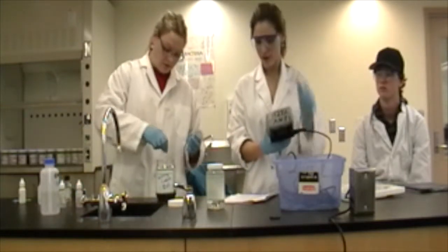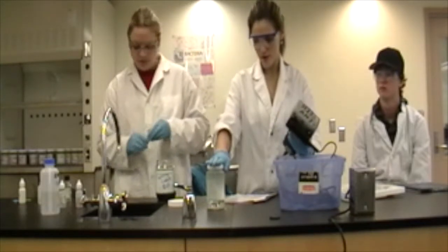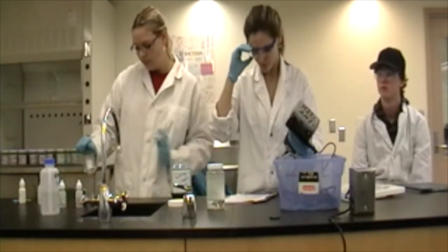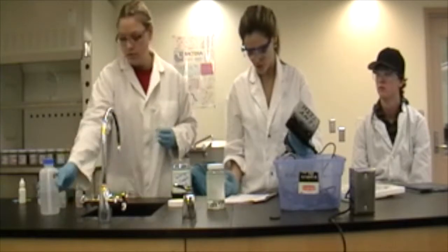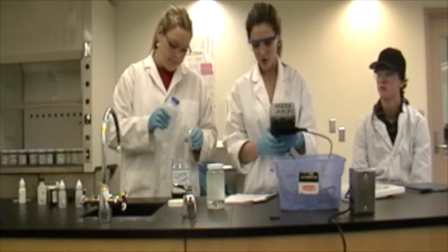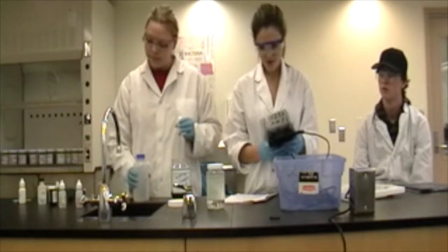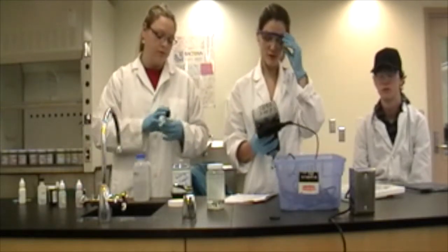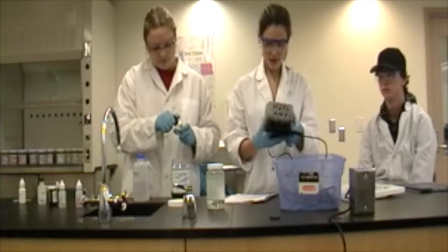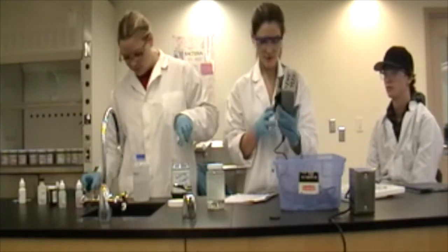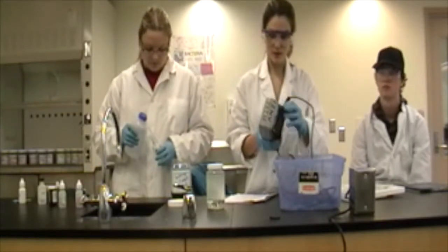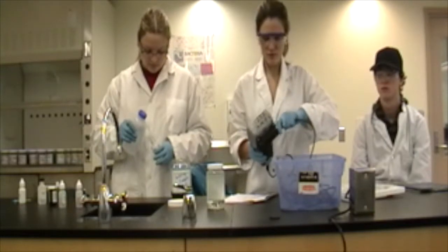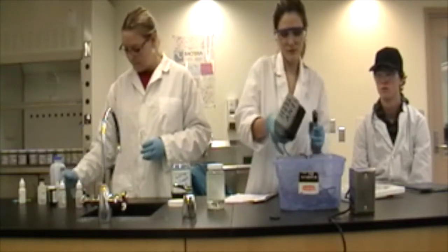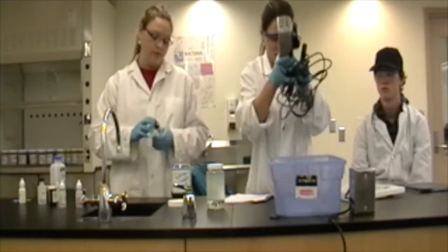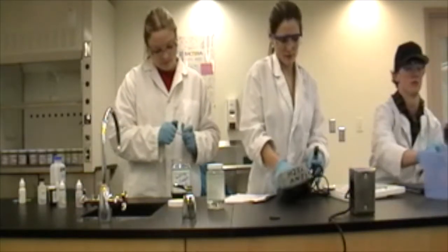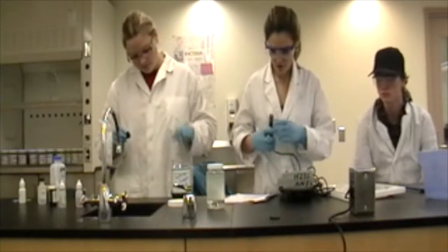Okay, so now, since we know what the DO is for this sample, we're going to calibrate the DO meter. First step, you want to check the physical condition of the meter before you even turn it on. So let's take a look. Make sure everything's plugged in, not broken. I'm going to take out the probe and check the physical condition of the probe.